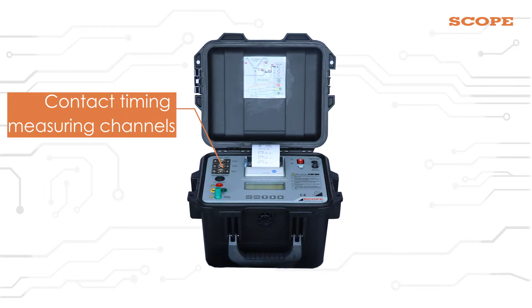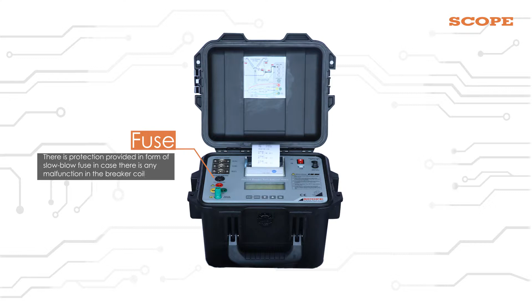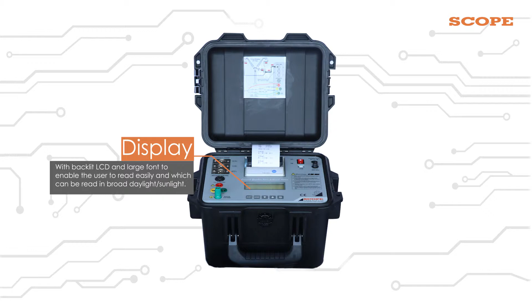These are contact timing measuring channels. There is protection provided in form of slow blow fuse in case there is any malfunction in the breaker coil. It has a display with backlit LCD and large font to enable the user to read easily and which can be read in broad daylight or sunlight. Breaker control section, it is used to issue the command to the circuit breaker.